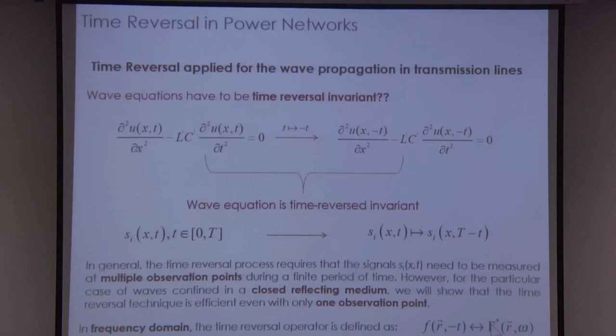Okay, now I'll show you how we apply it to the fault location problem. We need to consider some hypotheses. The first is that, as I mentioned, we need to keep the topology of the system unchanged. However, when a fault happens in the network, it changes the topology, so it seems we probably cannot apply it, but there's a very important feature here.